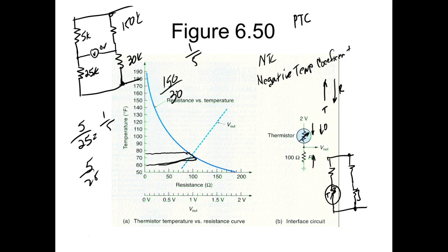And what I can do, of course, is this right here could be variable, and this right here could be a sensor that goes from 50 ohms up to 25K. And I could establish a reference. If it was a temperature sensor, I would establish a reference. The easiest reference to establish is 0. All we have to do is get a glass of ice water, shake it around a little bit, get it down pretty close to freezing, stick my sensor in there, and adjust this to measure 0. But we have to start off with a reference, right? We have to.